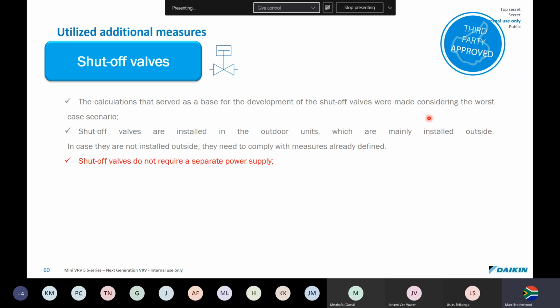If you want to put them inside and have a louvered box to comply with the leaks, you have to have certain dimensions. And the shut-off valves don't require separate power supplies. I presume they work very similar to solenoid valves, like on chillers, where there'll just be a relay that de-energizes a coil, and the coil will drop with a spring, and it will do a pump down in the liquid line while the compressor is running, and then the compressor should go out on a low pressure alarm.